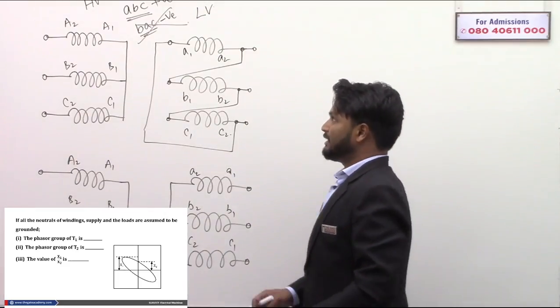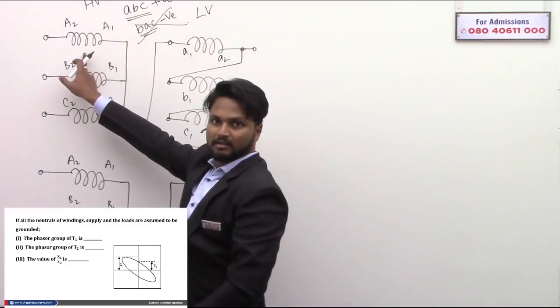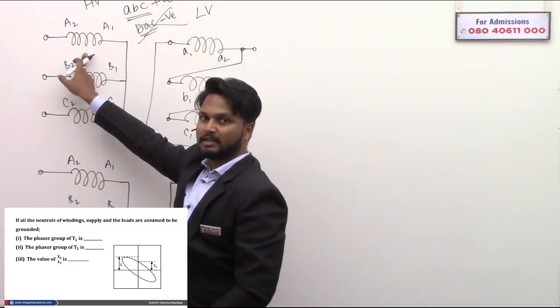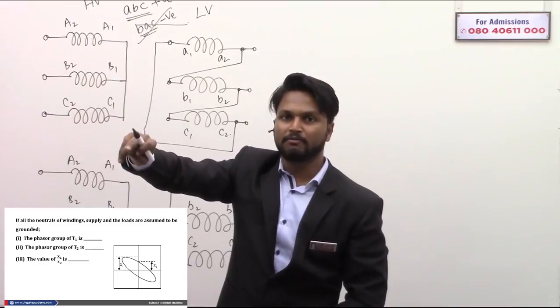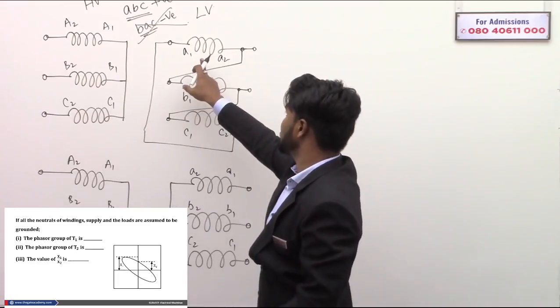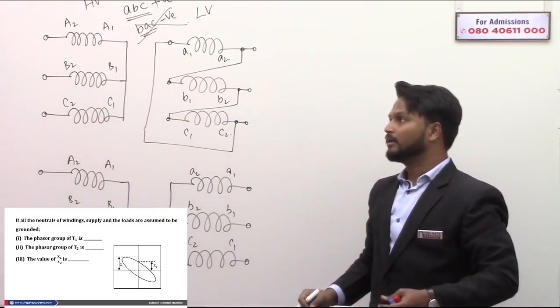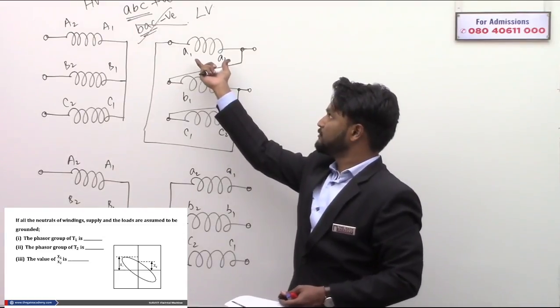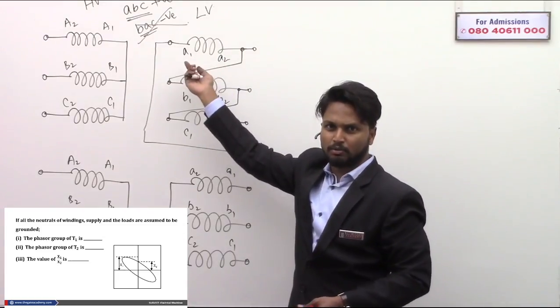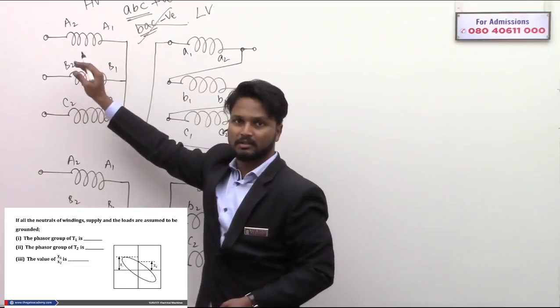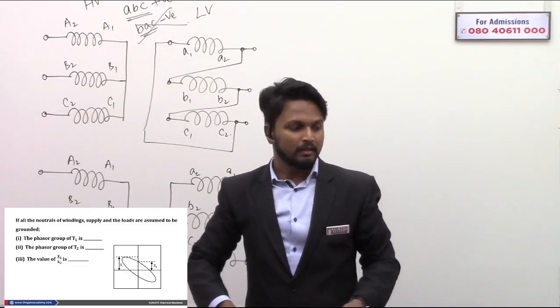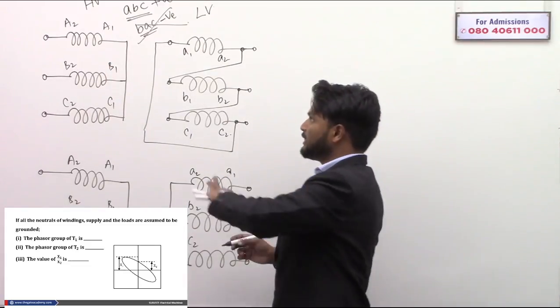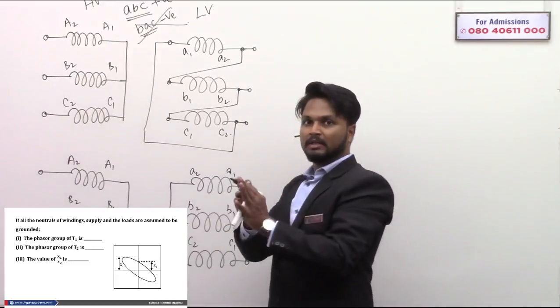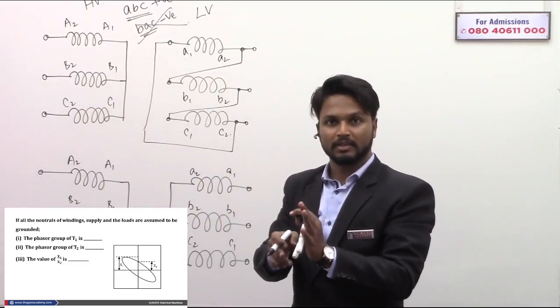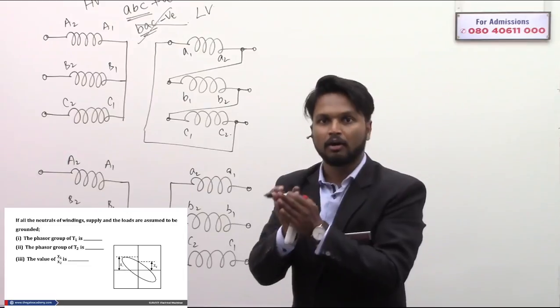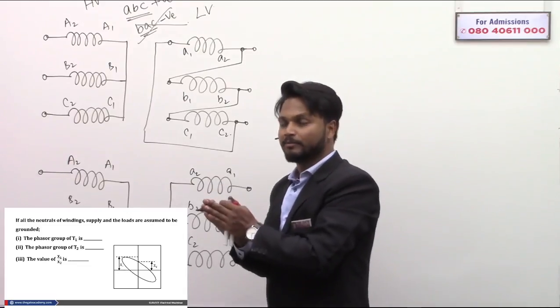The phase voltage in HV side, that is phase A, will be in phase with the phase voltage in LV side. So on the LV side, this phase voltage between A1 and A2 will be in phase with A1 A2 on the HV side. Either they will be in phase, or at a phase of 180 degrees - either parallel or anti-parallel.